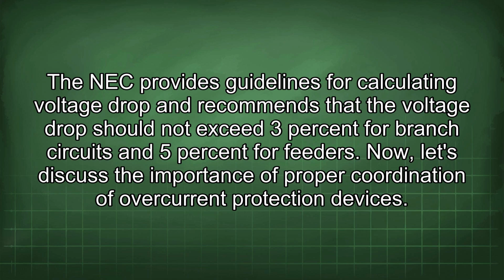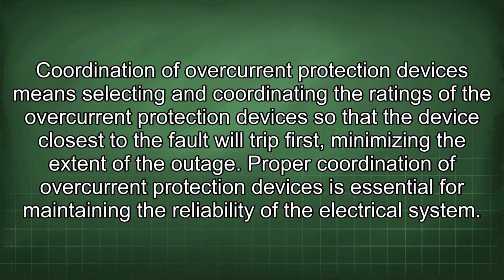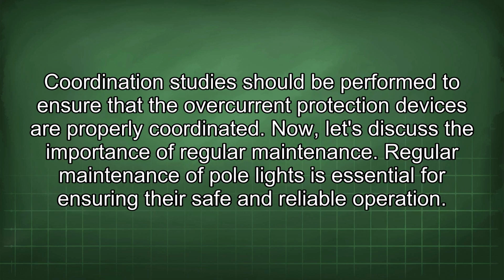Now let's discuss the importance of proper coordination of overcurrent protection devices. Coordination of overcurrent protection devices means selecting and coordinating the ratings of the overcurrent protection devices so that the device closest to the fault will trip first, minimizing the extent of the outage. Proper coordination is essential for maintaining the reliability of the electrical system. Coordination studies should be performed to ensure that the overcurrent protection devices are properly coordinated.